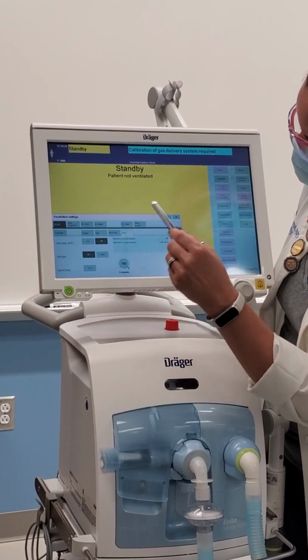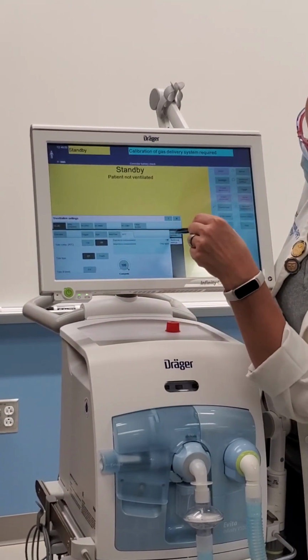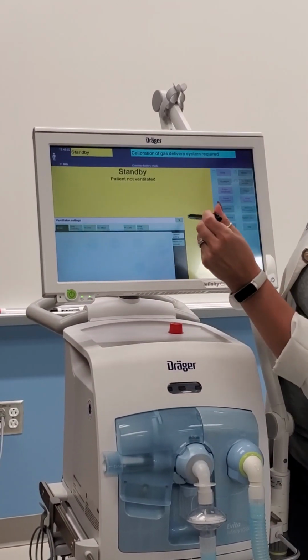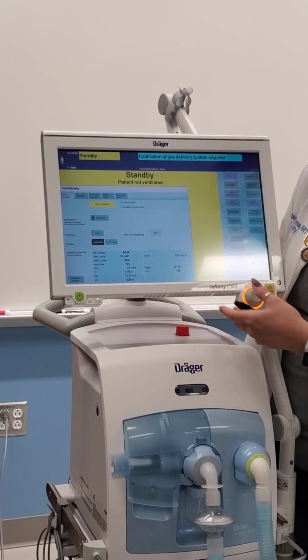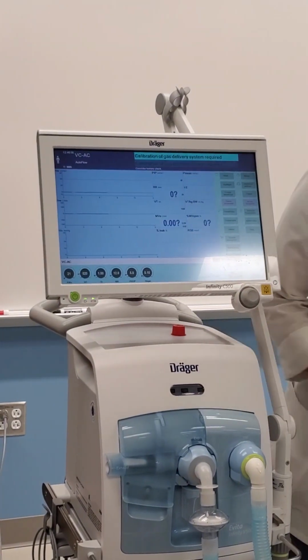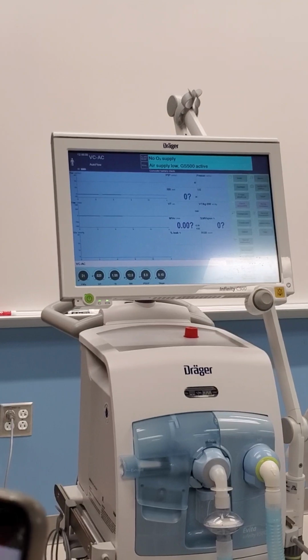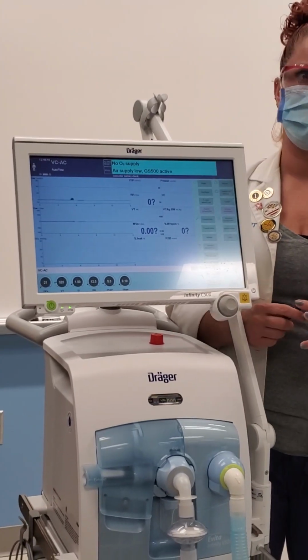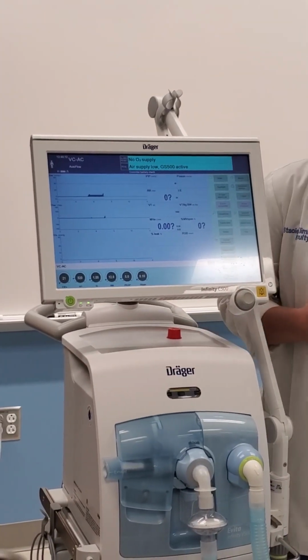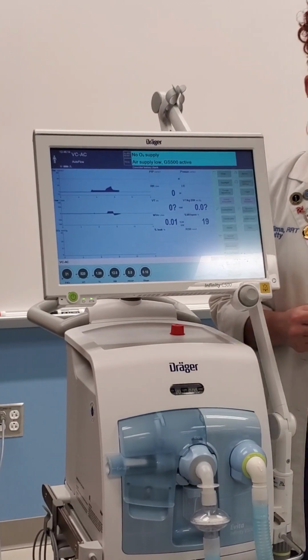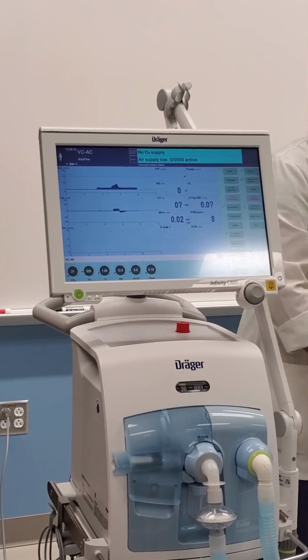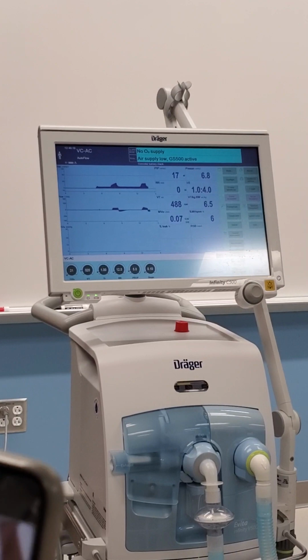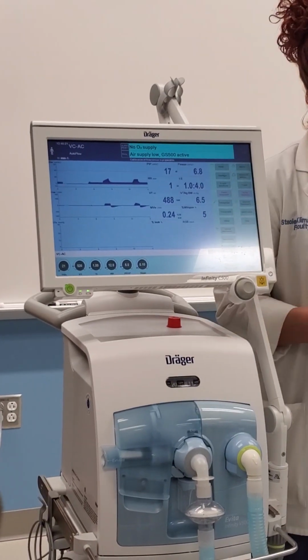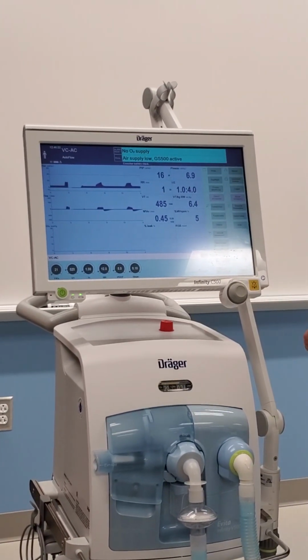Okay, let's go back to general settings, here we go. I'm going to start it up. So, start ventilation. But did you notice the whole time it was connected and the vent didn't sense that? That's really important, because if you're done with the ventilator or setting it up, you only attach it to the patient when the vent is running with the settings that you set. Okay?